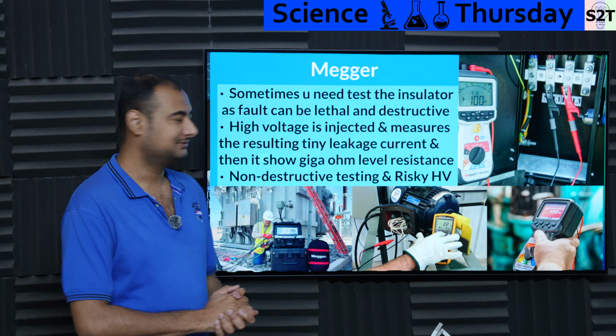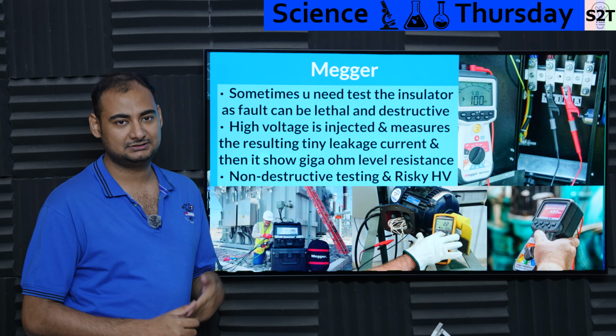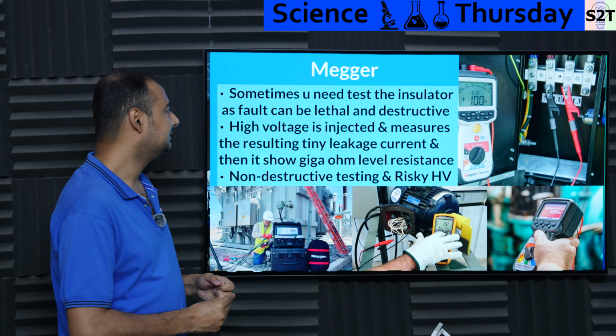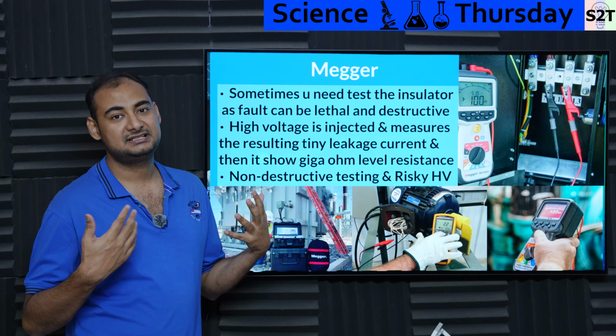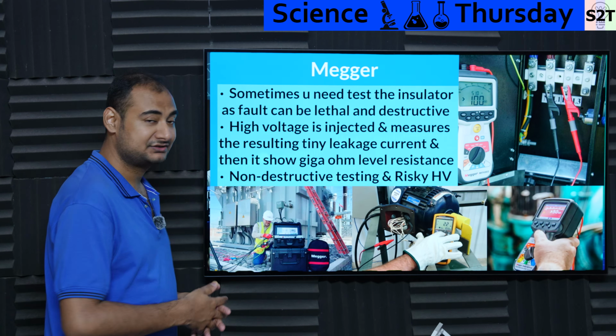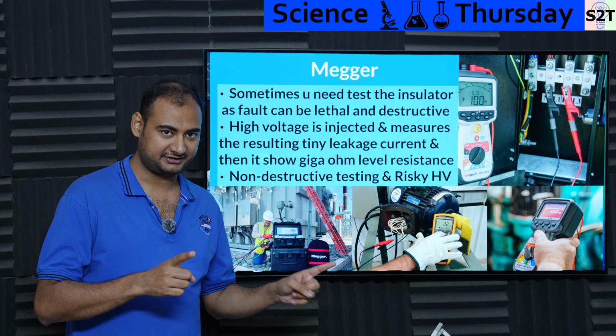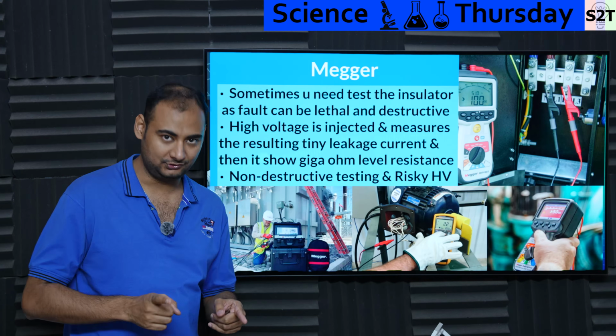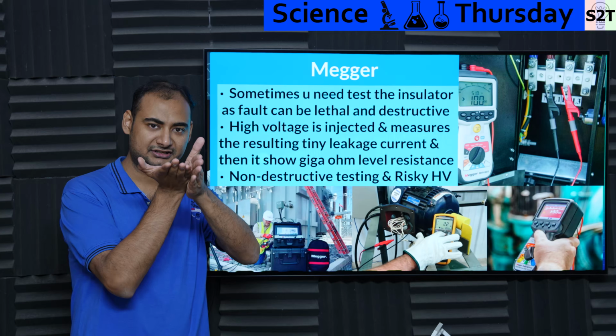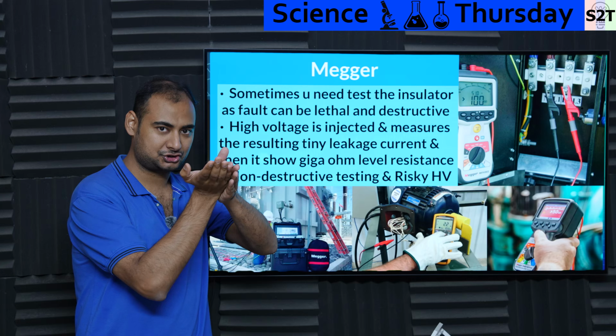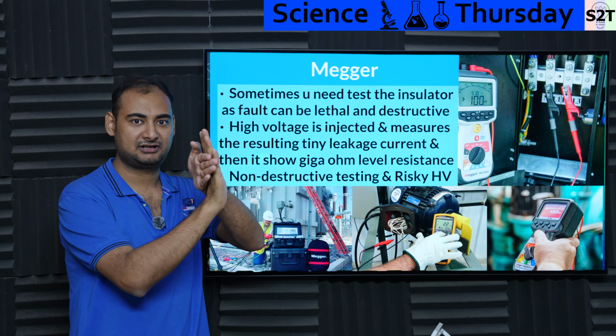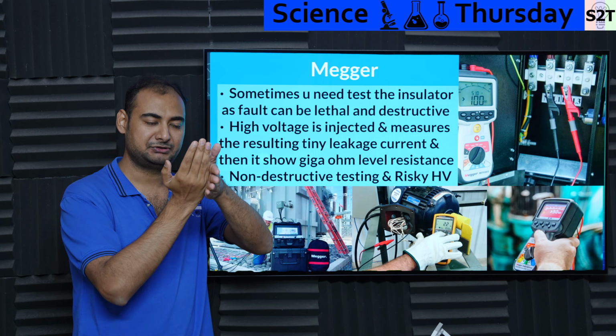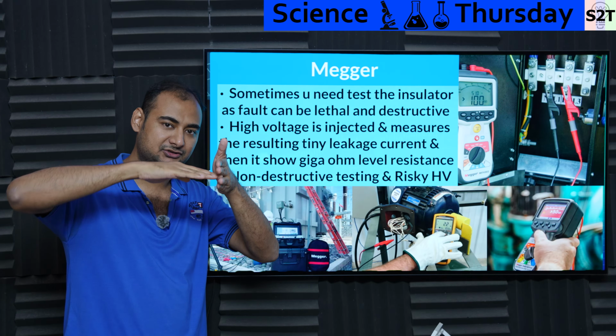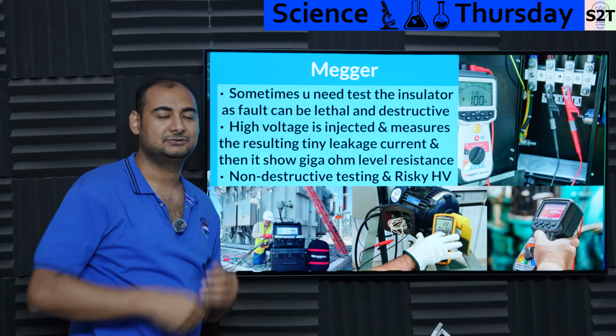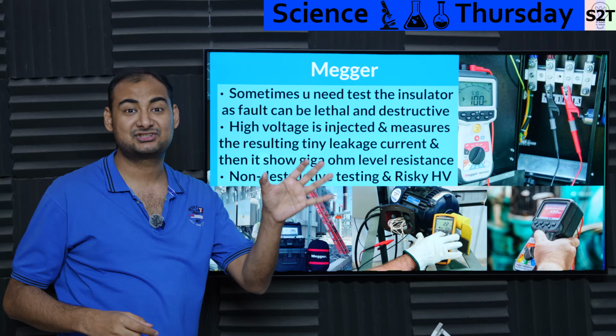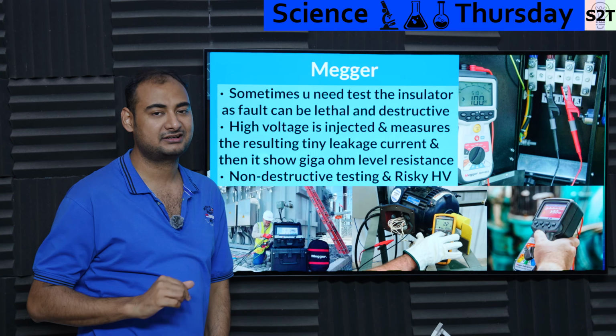Then we have the Megger, also called a Megohmmeter, sometimes called an insulation tester. You have to understand that conductor cares about current, insulator cares about voltage. You have an insulator, you have a conductor. The conductor is trying to push, basically there's human flesh here, and the insulator is in between. The voltage is trying to push through the insulator. That's why your insulation becomes thicker the higher the voltage, not with current.